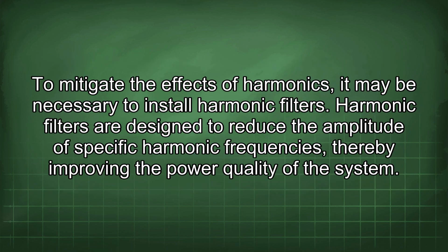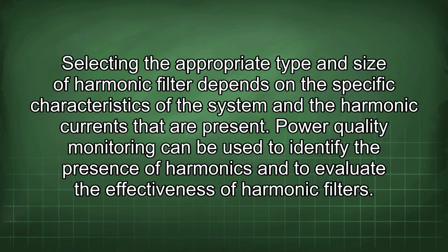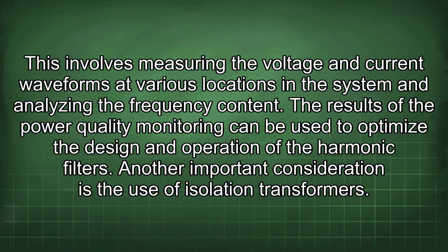To mitigate the effects of harmonics, it may be necessary to install harmonic filters. Harmonic filters are designed to reduce the amplitude of specific harmonic frequencies, thereby improving the power quality of the system. Selecting the appropriate type and size of harmonic filter depends on the specific characteristics of the system and the harmonic currents that are present. Power quality monitoring can be used to identify the presence of harmonics and to evaluate the effectiveness of harmonic filters. This involves measuring the voltage and current waveforms at various locations in the system and analyzing the frequency content. The results of the power quality monitoring can be used to optimize the design and operation of the harmonic filters.